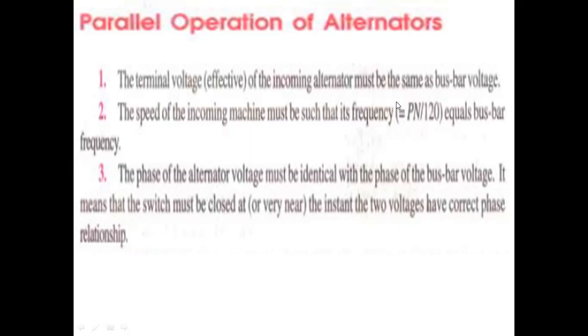If so many alternators are connected along with the loads, then we are not bothered about the power delivered by the incoming alternator, and we do not bother about the voltage and frequency because they will remain the same. This type of connection is called an infinite bus bar. It is never advisable to connect a stationary alternator to a live bus bar because the stator induced EMF will be zero and short circuiting will result.